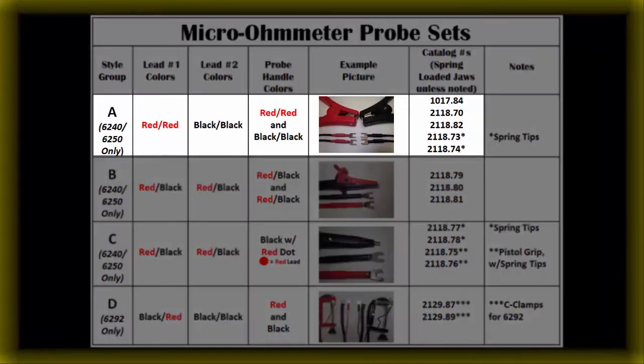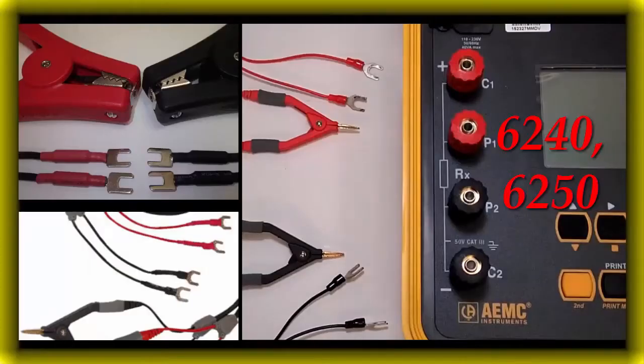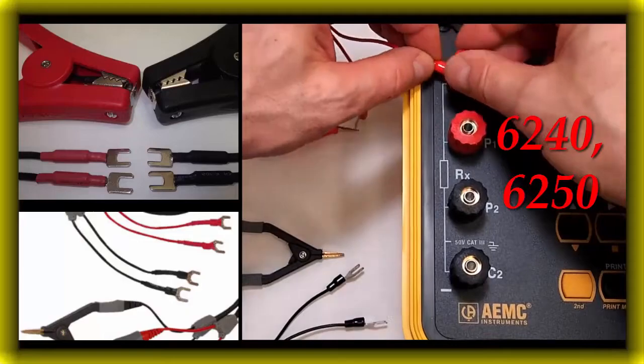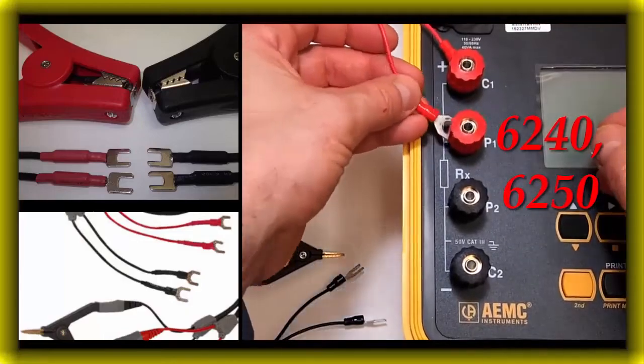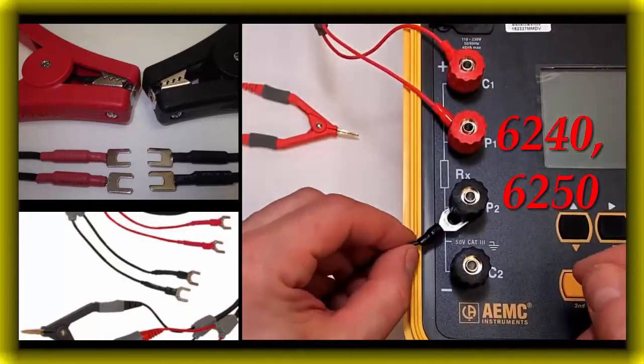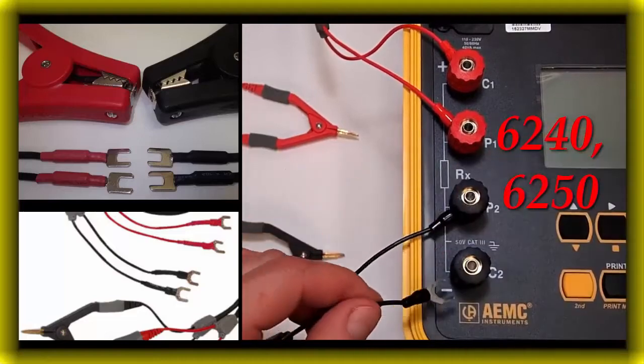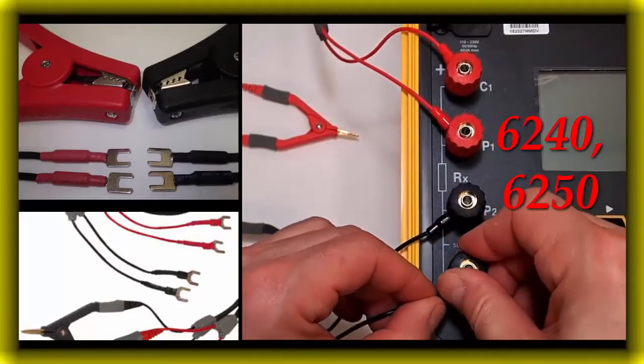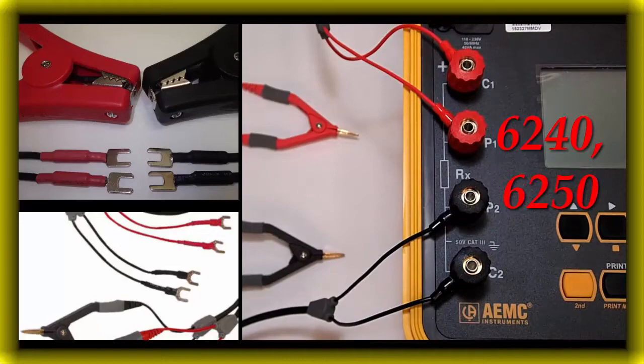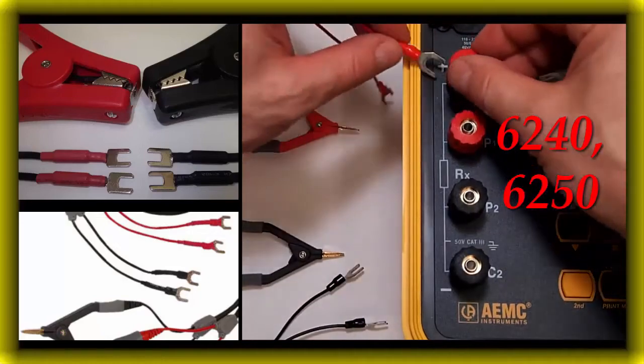Style Group A for 6240 and 6250. When using the 5 part numbers from the Style Group A, where the leads are red, red, and black, black, then the connections are going to be straightforward, and the color coding will match up to the instrument's terminals. Note, these leads are not approved for use with the model 6292.